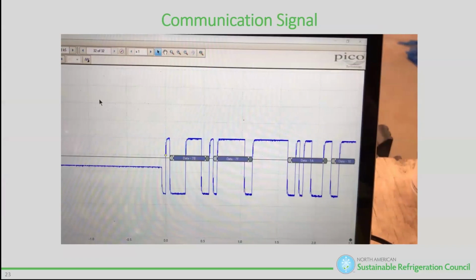So we added 5 more cases. When we added those 5 more cases, the signal went bad, so we knew the problem was between 21 and 25. Then we broke it in half again. We were able, within 40 minutes, to find a broken wire in conduit on the Modbus circuit.